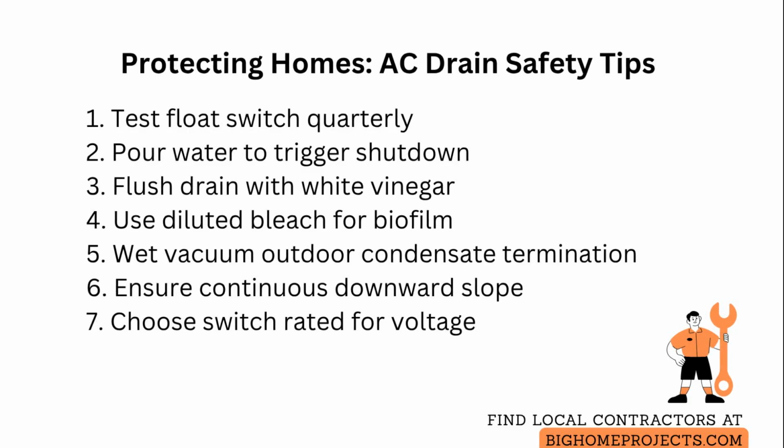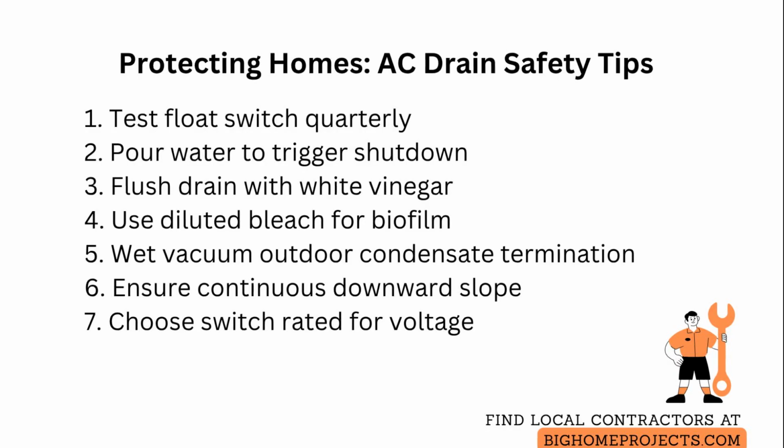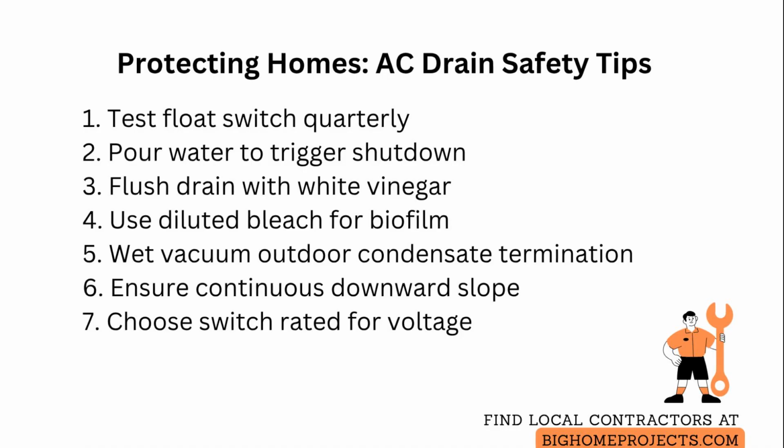And when replacing a switch, choose one rated for your unit voltage and with a manual reset option if you need to run diagnostics. If your system uses a condensate pump for gravity-challenged installations, ensure the pump has its own float or safety switch and test both pump operation and the backup safety device.